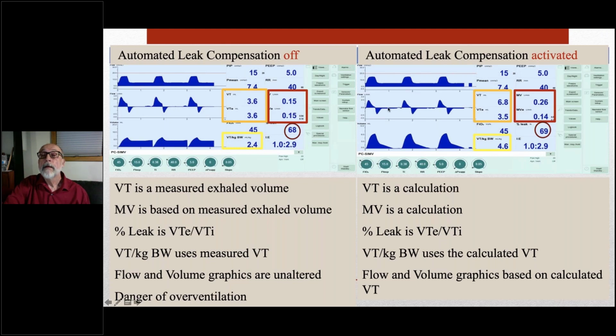Okay. Now, that's a problem, right? Because this is not real. We're relying on this exhale tidal volume that is affected by this very large leak. So when you turn on leak compensation, and that's something that you have the choice of doing, but I would strongly recommend that you use it. And this is the reason.